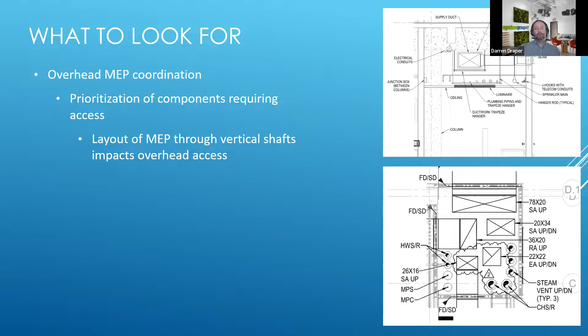That top version is actually a prioritization matrix, or prioritization section view, showing where things that require maintenance need to be versus things that do not—to make the BIM coordination process easier for the general contractor and their subs. The general idea is to put the components requiring the most maintenance as low as possible, close to the ceiling, so an O&M person can get on a ladder and reach that equipment or device to do the needed maintenance activity—isolating a plumbing line, accessing a controller on a terminal unit, popping out a lighting fixture to replace a ballast, and other critical maintenance tasks. If it's not in a place where it can be maintained, it probably won't be maintained, and that's detrimental to the long-term operation of the building.